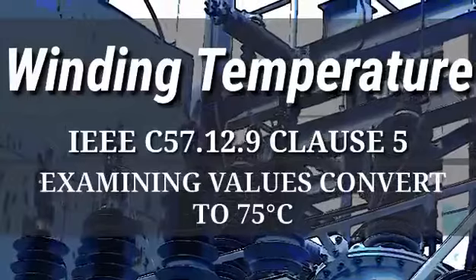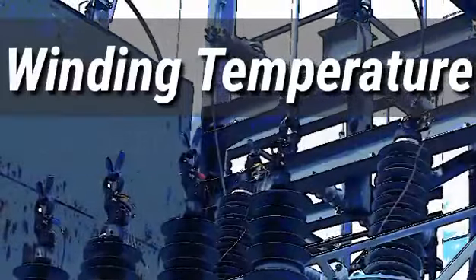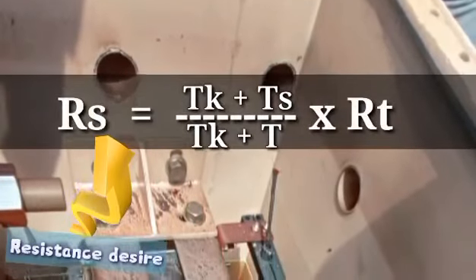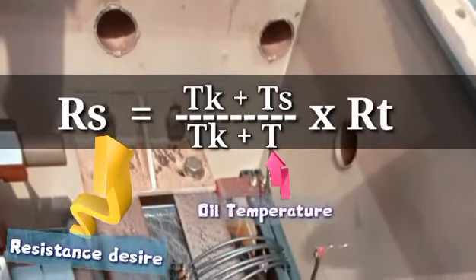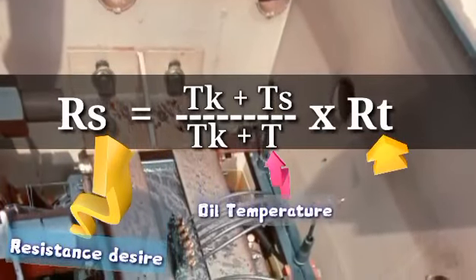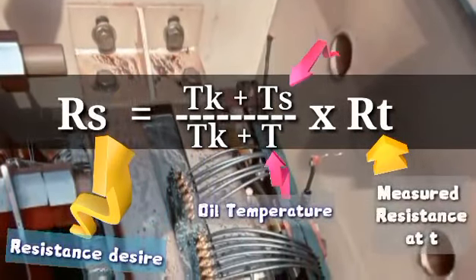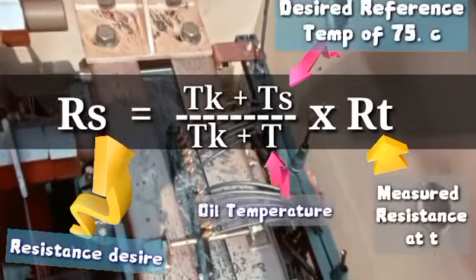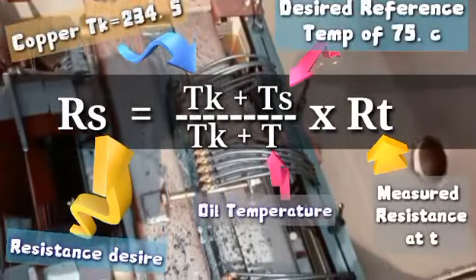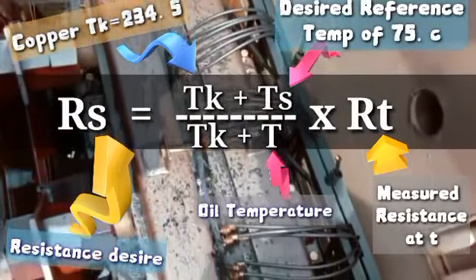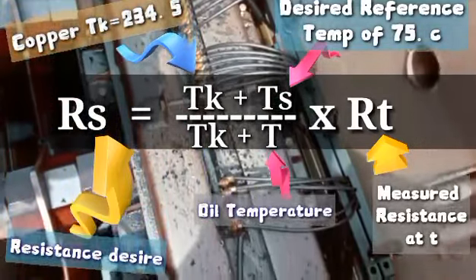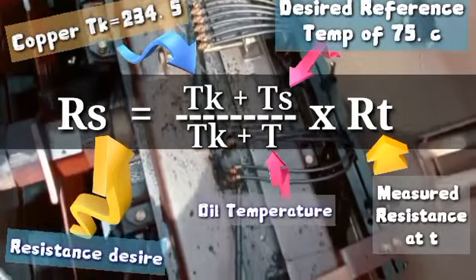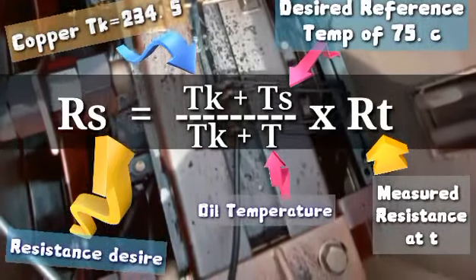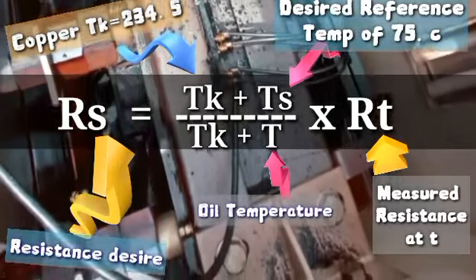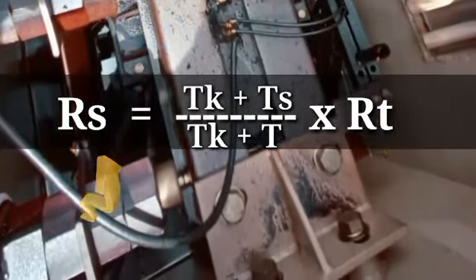The measured values are converted to 75 degrees Celsius, where the formula is as follows. Rs is the resistance at the desired temperature Ts in ohms. T is the oil temperature as measured. RT stands for the measured resistance at T. Ts equals 75 degrees Celsius, which is our desired reference temperature, and the constant for copper equals 234.5. Although there are also testing sets where measured values will be automatically corrected to the reference temperature, the only thing to do is to input the reference value as customer-defined, in line with which standard and what type of material is being used.